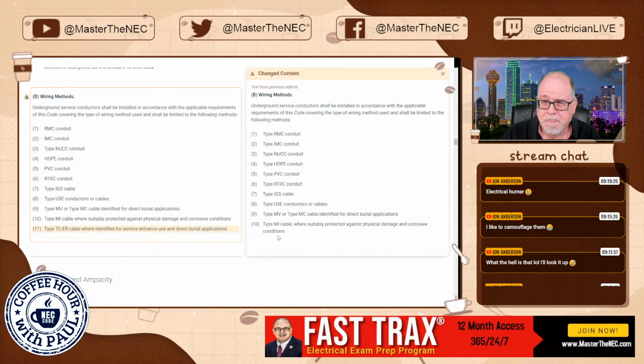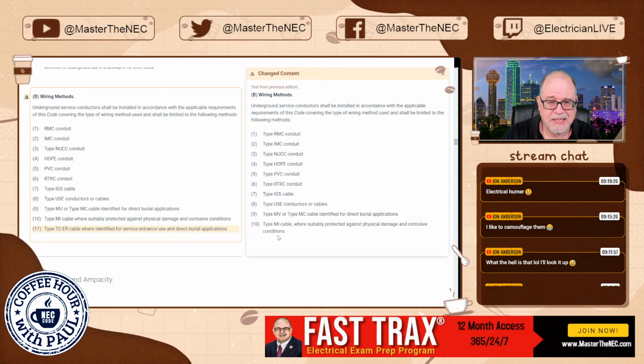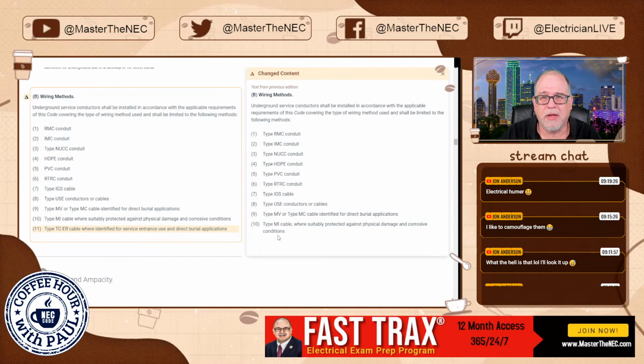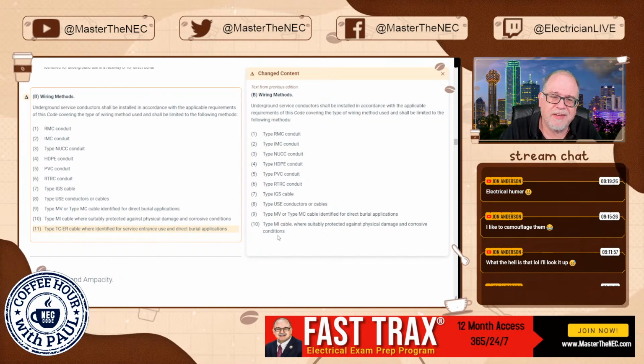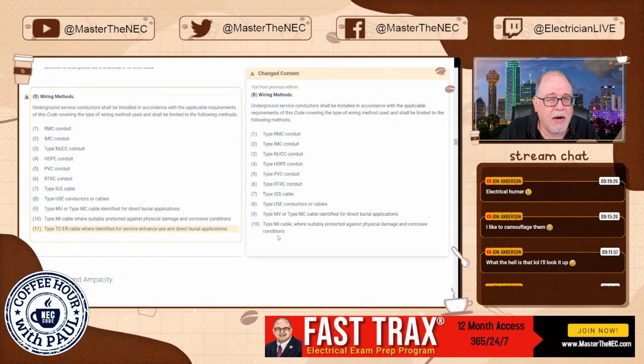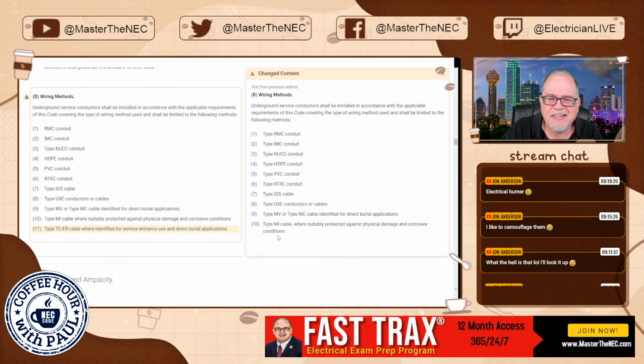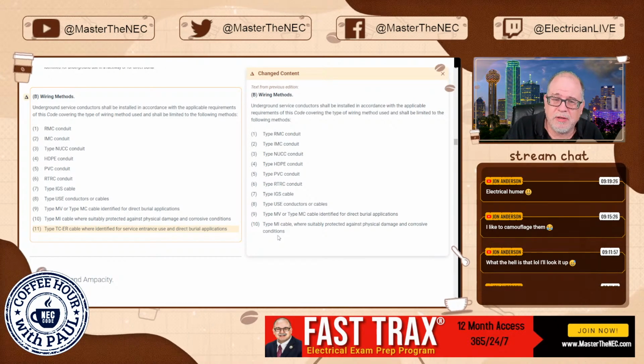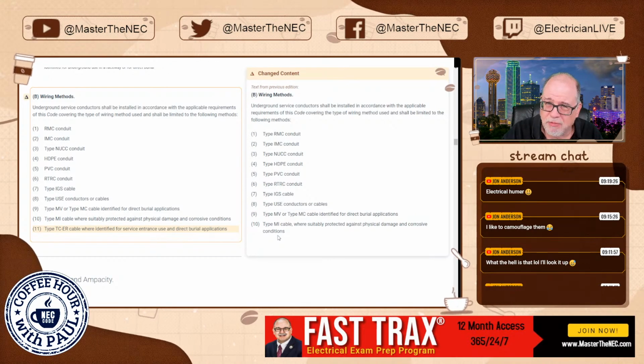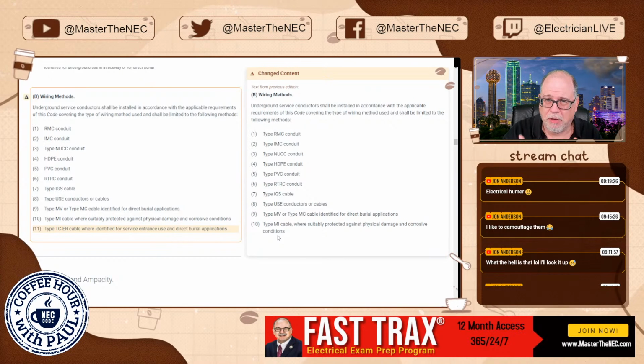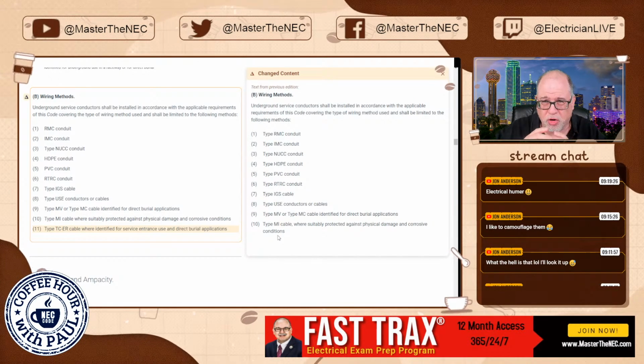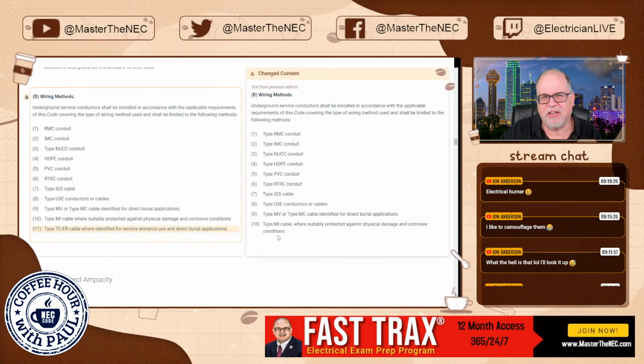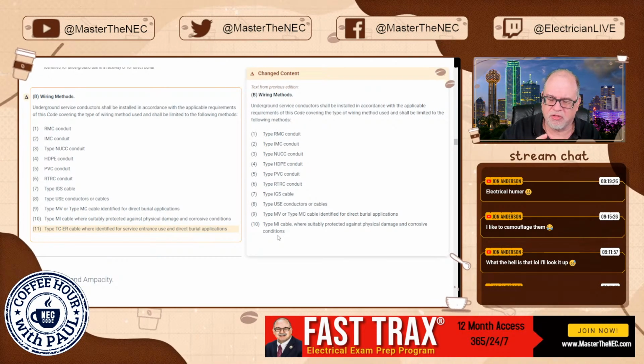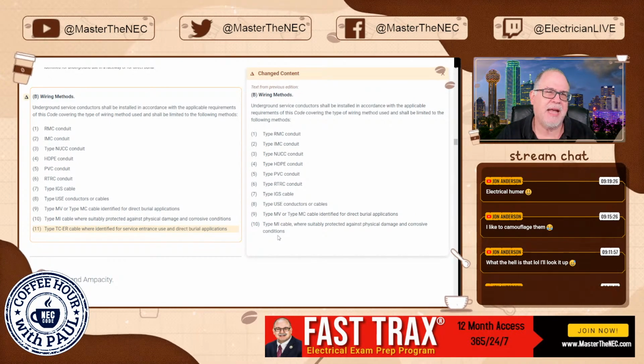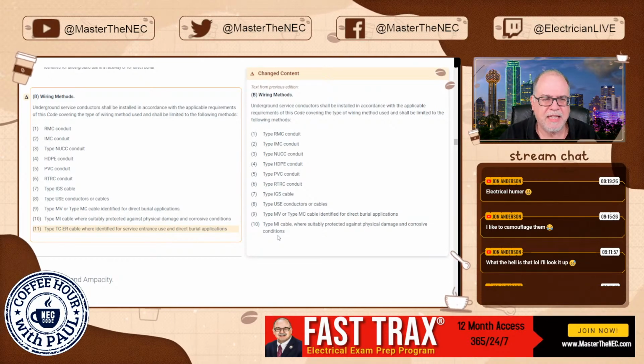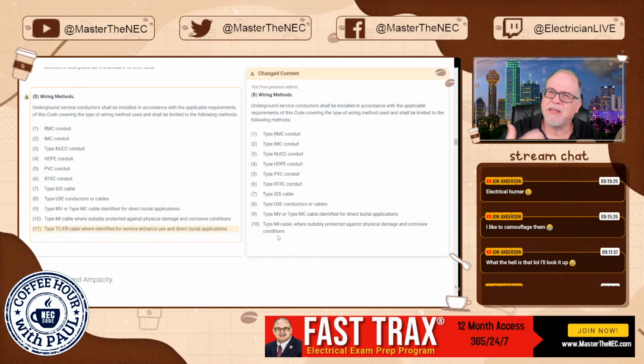Now, I'm going to tell you that tray cable is basically identical to SE cable, service entrance cable. One of the significant differences is that service entrance cable requires a fiberglass binder, whereas TCER does not. A binder is optional in tray cable, but if it needs to maintain its roundness, then the binder is going to help keep that roundness, so that when it's extruded with the jacketing over the conductors, it doesn't sink into the interstices, those are the grooves, and create something that looks more like a square than it would be round, right? So that's up to the manufacturer. Roundness is in the eye of the beholder, but with the extrusion, you want it to be round in nature.